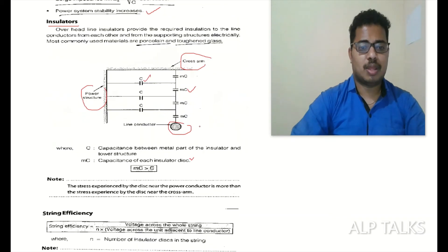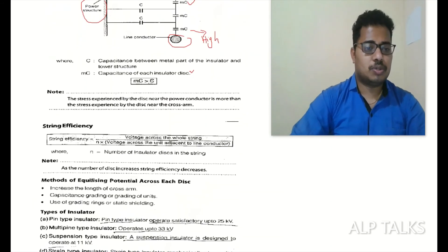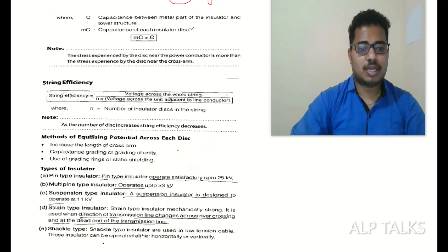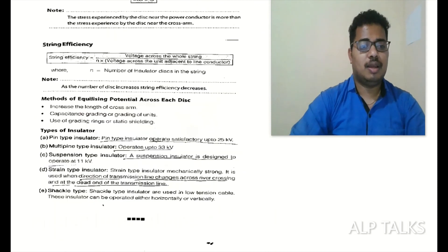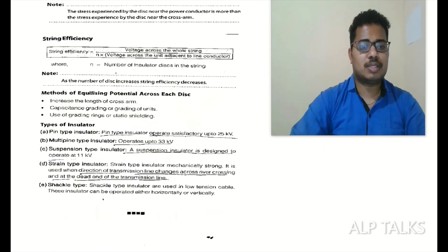Generally MC is greater than C. The stress experienced by the disc near the power conductor is more than stress experienced by the disc near the cross arm. This disc will offer highest capacitance value, so there will be a factor for string efficiency. String efficiency is voltage across the whole string divided by n into voltage across the unit adjacent to the line conductor, where n equals number of insulator discs in the string.